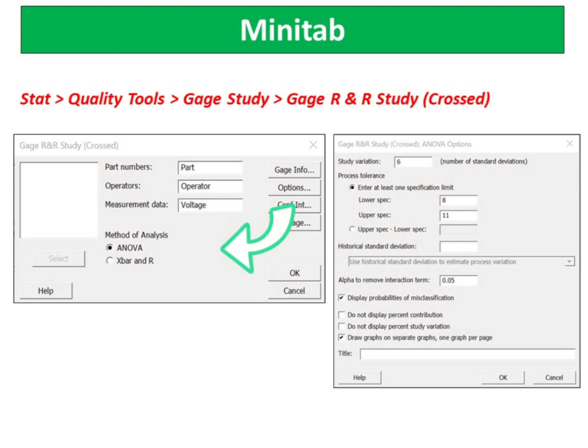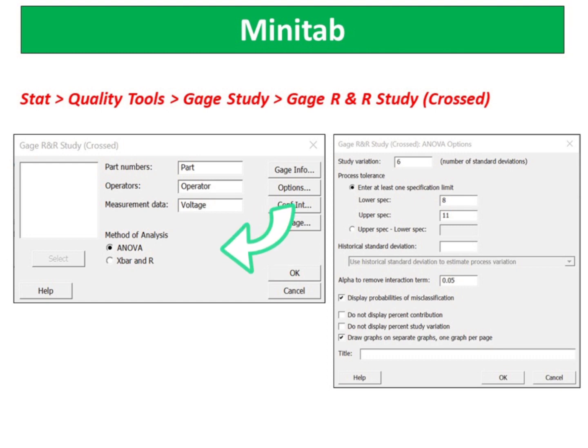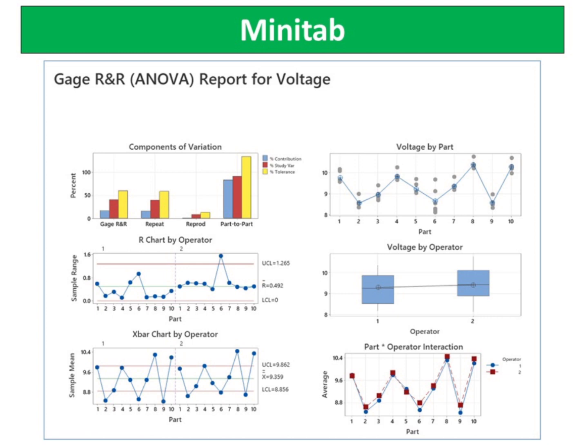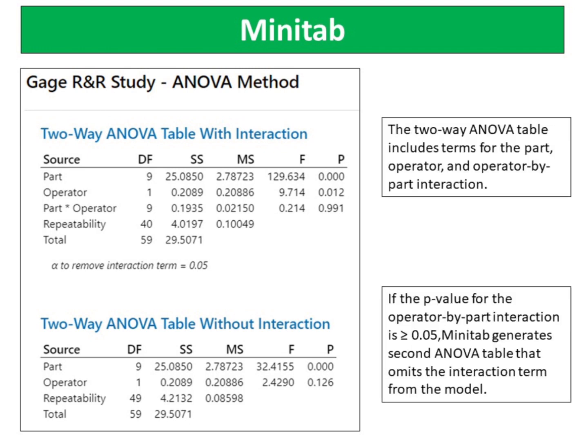What is the difference between the two methods? For the ANOVA method, this provides an additional test for the interaction between the operators and the parts, beyond just the operator main effect. However, for the X-bar R method, or average and range method, there is no interaction study between the operators and the parts. Minitab uses the analysis of variance (ANOVA) procedure to calculate variance components, and then uses those components to estimate the percent variation due to the measuring system. The two-way ANOVA table includes terms for the part, operator, and operator-by-part interaction. If the p-value for the operator-by-part interaction is greater than or equal to 0.05, Minitab generates a second ANOVA table that omits the interaction term from the model.